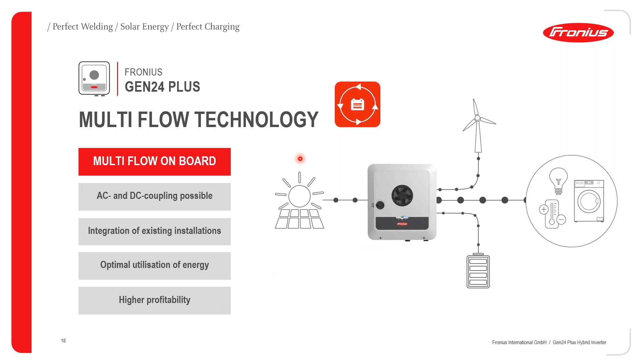As we can see in this illustration, we have the possibility to get energy from the PV side and from the battery side, or from the grid side, and all this can be combined internally by the Gen24 Plus inverter to supply your loads. So the energy multi-flow concept therefore allows the AC and DC coupling of the Gen24 Plus inverters. As a result, you can easily integrate the Gen24 Plus inverters into existing PV installations, and this allows optimal utilization of the generated energy, and consequently that leads to higher profitability. This is a concept that is integrated as a standard in all Gen24 Plus inverters.